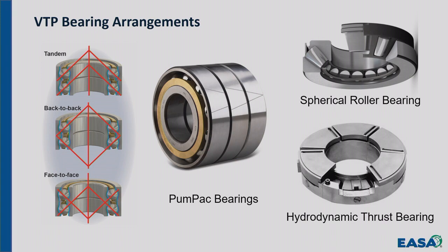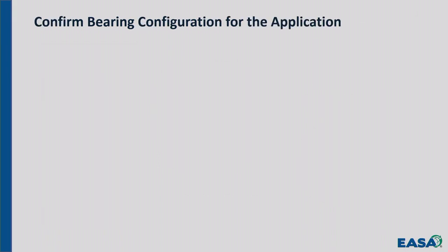These vertical motors sometimes are configured at the factory for one application and have been moved to some other application, bought, sold, or whatever. Just because it is the same frame size, horsepower, speed, and it's got two bearings in it, doesn't mean that it's configured for another application. In one application, that might be one bearing up and one down because it's subject to upthrust. In another application, that could be two bearings both down because it's a very deep well pump and it has a much higher axial load, and they don't worry about upthrust, but they've got to be able to hold that shaft. Okay? The same motor can be configured lots of different ways for different applications.